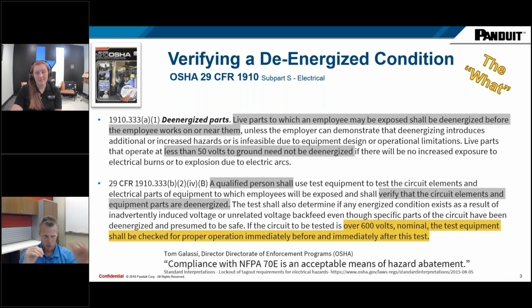So a couple quick blurbs in OSHA, 29 CFR 1910. De-energized parts, right? Live parts to which an employee may be exposed shall be de-energized before an employee works on or near them. Less than 50 volts, don't worry about it, but 50 to anything above 50, you gotta de-energize. And then second, a qualified person, going back to Caitlyn's statement earlier, it's a qualified person. It just can't be anybody that's authorized or anybody that's walking by. You got to be trained in this and how to do it and what it means. But a qualified person shall verify that the circuit elements and equipment parts are de-energized. So de-energized comes up quite a few times in OSHA, 29 CFR 1910.